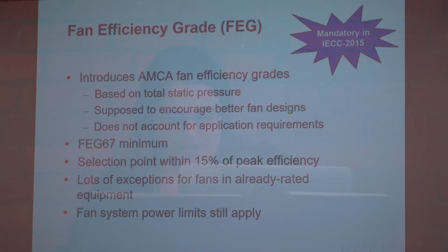Okay, so here's that fan efficiency grade. This is trying to attack fans larger than 5 horsepower. Below 5 horsepower, there is no requirement because FEG really falls away below 5 horsepower. The biggest change to design practices is to select within 15% of your peak efficiency. So in systems where you have a really wide swing in pressure that the fan has to operate against, that provision can actually be very difficult to meet in some cases. So it seems to be creating some winners and losers in terms of fan choices, and that's why we're so keen to get a replacement for that.